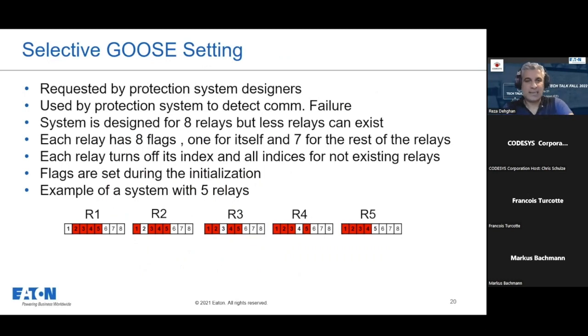Yeah, selective GOOSE setting, that was another thing. This one was asked for by the protection system designer. These bits are used to detect communication failure between the relays in the system. The system is designed for 8 relays, but there are some cases where you may use fewer than 8 relays. So there should be a way to tell the protection relay that some of the relays are not there. It's not because there's a COM failure, it's just that those relays don't exist.